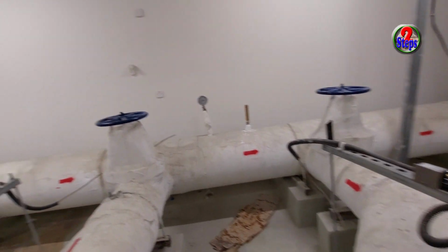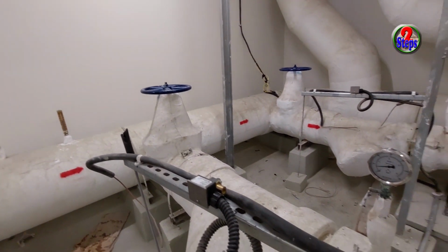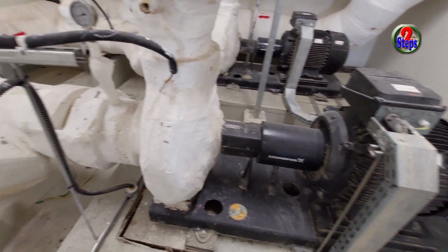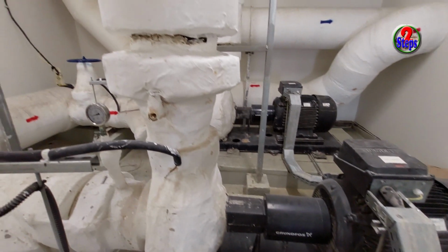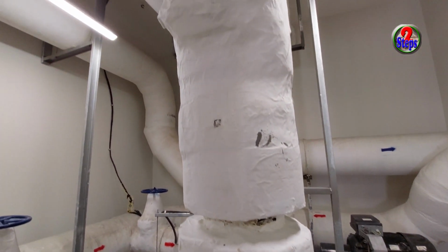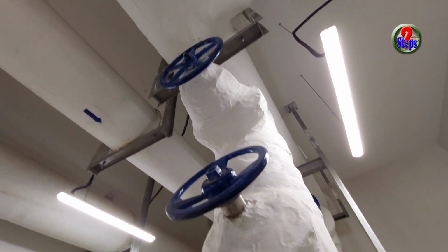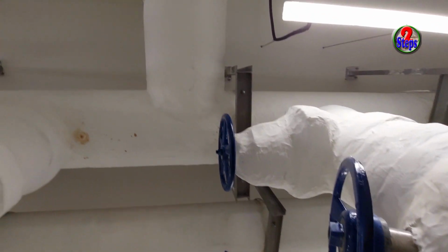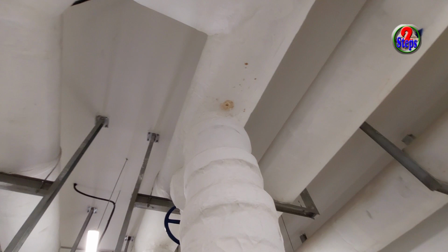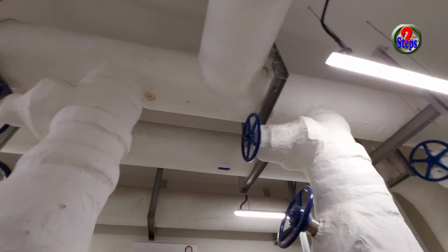This pump connects to the secondary pump suction header. Typically the same: isolation valve, strainer, then rubber flexible connector, pressure gauge, then pump. After that, NRV, rubber flexible connector, then DRV, isolation valve, discharge header. The discharge header directly supplies water to the domestic area, I mean each cooling unit like AHU, FCU, trap unit, etc.